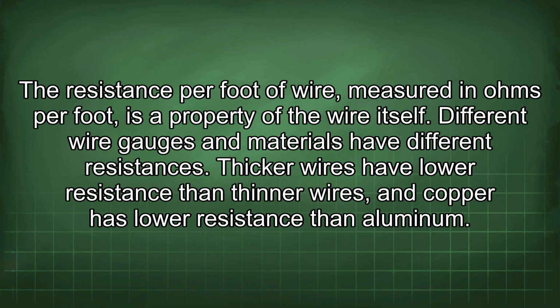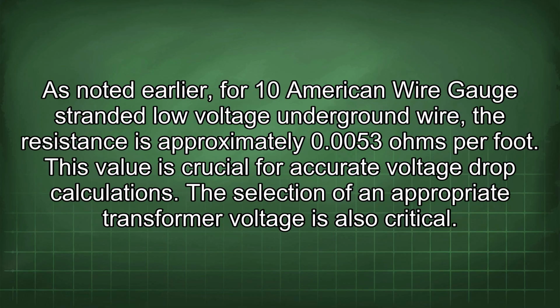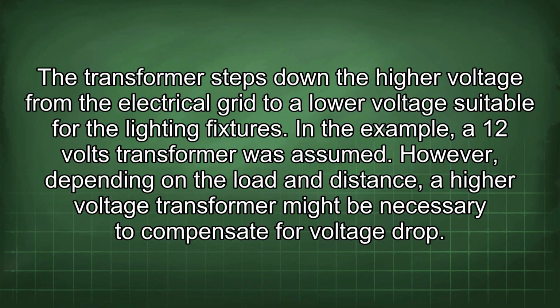This is simply because the current has to travel a longer distance, encountering more resistance along the way. The resistance per foot of wire, measured in ohms per foot, is a property of the wire itself. Different wire gauges and materials have different resistances. Thicker wires have lower resistance than thinner wires, and copper has lower resistance than aluminum. As noted earlier, for 10 American wire gauge stranded low voltage underground wire, the resistance is approximately 0.0053 ohms per foot. This value is crucial for accurate voltage drop calculations. The selection of an appropriate transformer voltage is also critical. The transformer steps down the higher voltage from the electrical grid to a lower voltage suitable for the lighting fixtures. In the example, a 12 volt transformer was assumed.